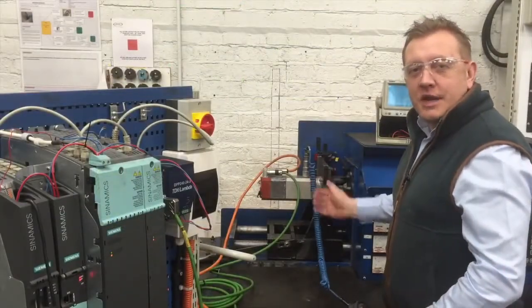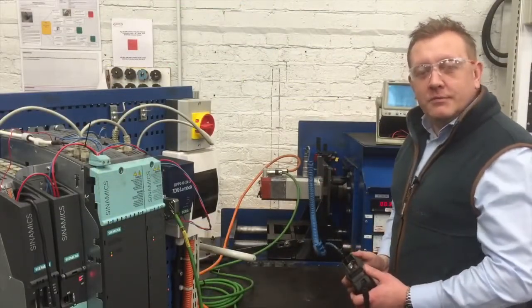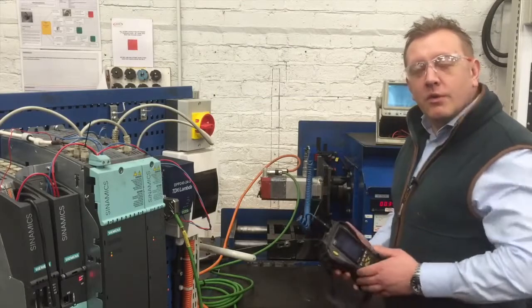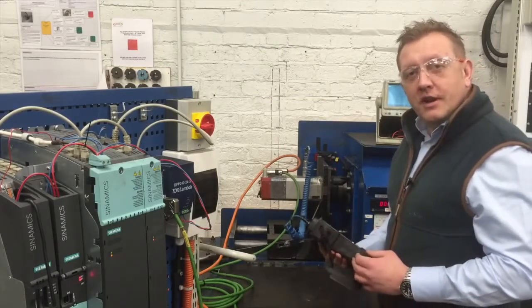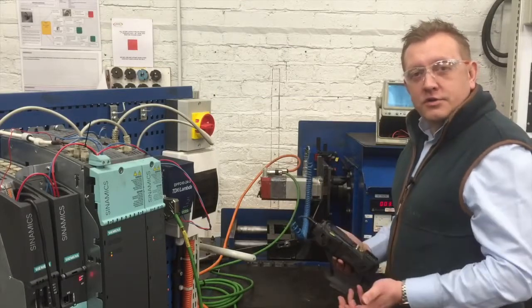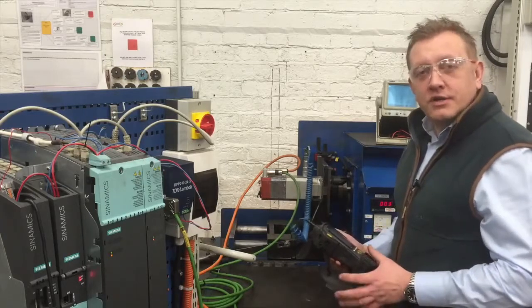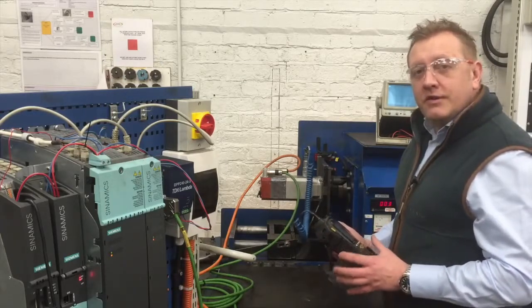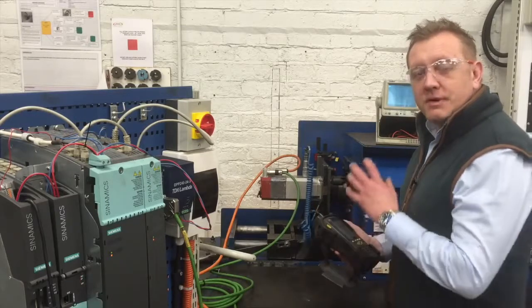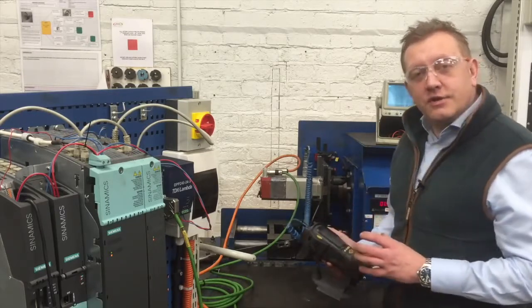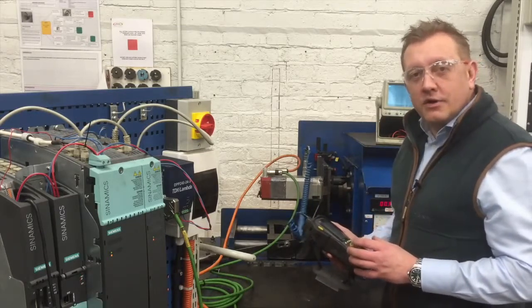This motor has now been fully tested and it meets Siemens specifications. What we are going to carry out now is a vibration analysis test to ensure subsynchronous rotational, twice rotational frequencies, and also bearing defect frequencies are checked, ensuring that this motor is mechanically sound as well as electrically sound before we send it back to our customer.